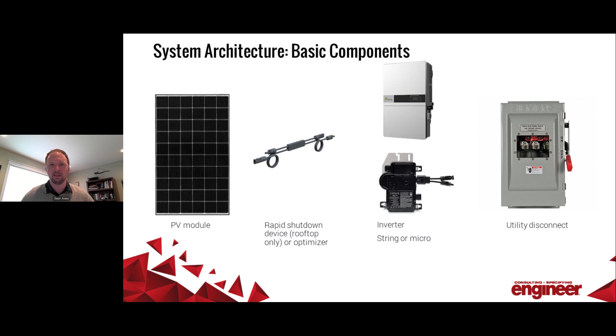And then finally, once you go there, you usually end up with the utility disconnect before you tie into the grid. The requirements of that vary a little bit by jurisdiction. Most often, if they are required, the utility wants you to have a viewing window on it, as shown in this picture here, so they can visibly see that the system is disconnected if they had to go in there and do any maintenance.